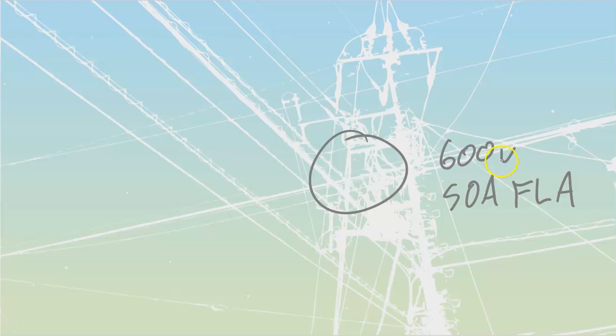Let's first examine what this would be if we didn't use the reduced voltage. If I had 5 times that, I would have a 250 amp inrush, right? 5 times 50 gets me to 250. That's a phenomenally large amount of current to be conducting. It is going to give us really fast acceleration and maximum torque, but we don't necessarily need that maximum torque. It says we're going to use an autotransformer set at the 80% tap.